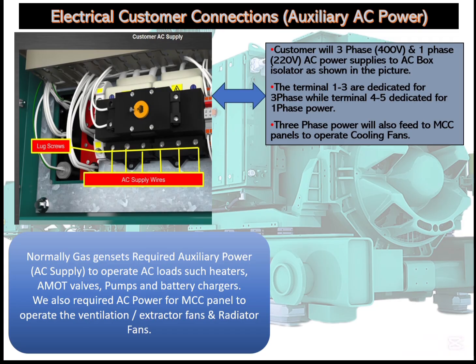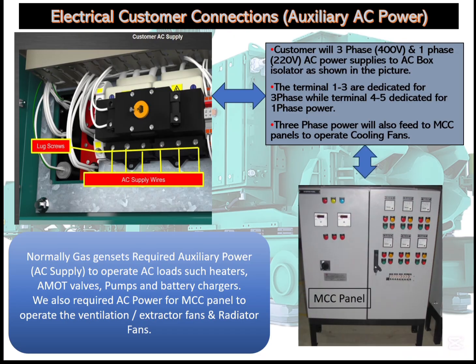This is the AC box, where we open. Here we connect cables for AC power, that is 3-phase AC power and single-phase AC power. That is the requirement of the genset for operation. When it's on standby, it will have heating elements that maintain the heating temperature, so that for quick start, we have circulation pumps and battery chargers. Then we also require AC power to operate our MCC panel. Inside the MCC panel, as I mentioned initially, we have ventilation or extractor fans, and if we are using a cooling tower or radiator, we have fans.